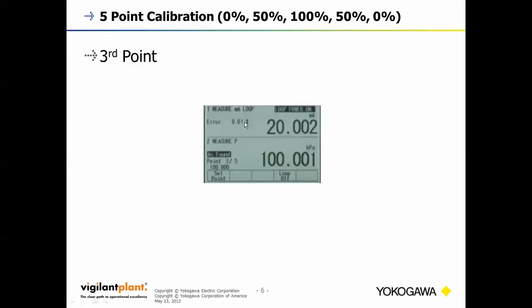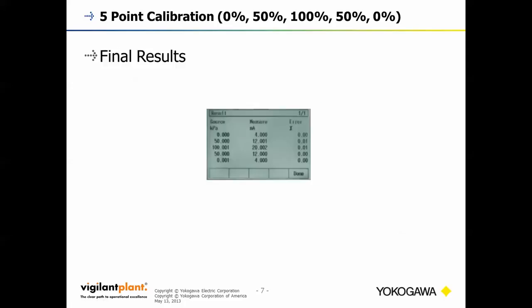So just to skip ahead, if we go to the third point, we've got a little bit of error, but again, the transmitter's reading almost 20 milliamps, and same thing on the calibrator, almost 100 kilopascals. So the error is still well within the tolerance, the 0.055% of the EJA110E, so it's well within that.